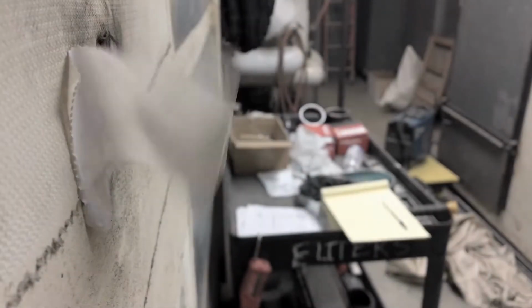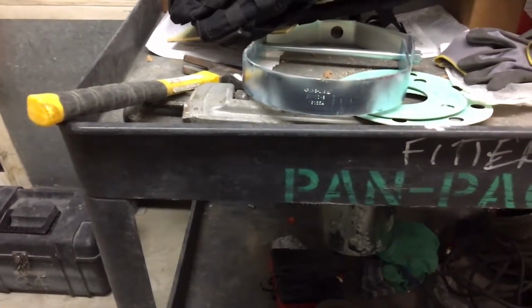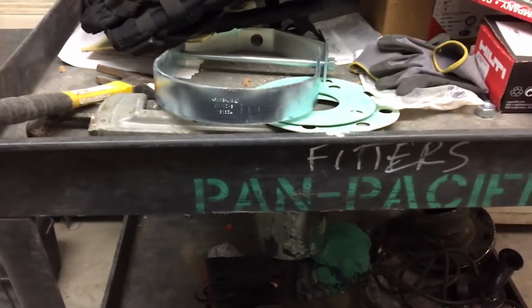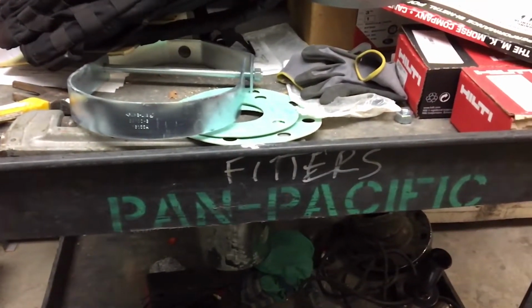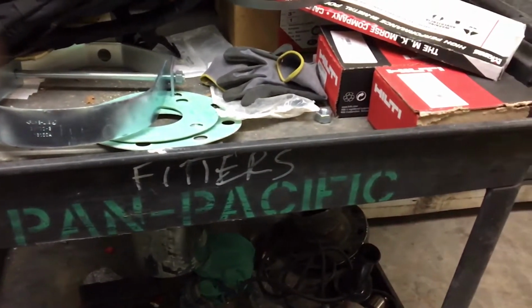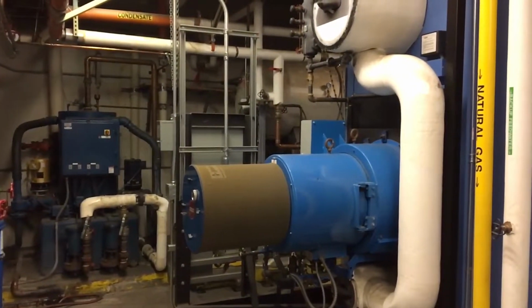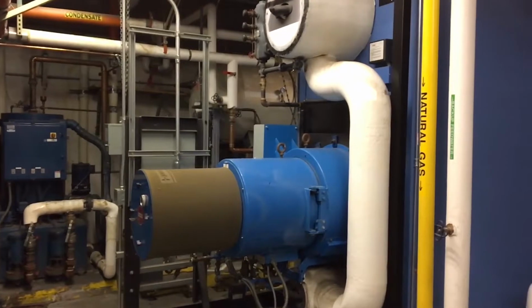The particular system being covered today is a 4-pipe piping system. Comfort is achieved by controlling the rate and manner in which heat is transferred from the body. Modern-day hydronic systems are comprised of 3 main parts. They are the heating and cooling sources, the distribution system, and the terminal units. This particular system uses a boiler to heat the water and a cooling tower to chill the water.